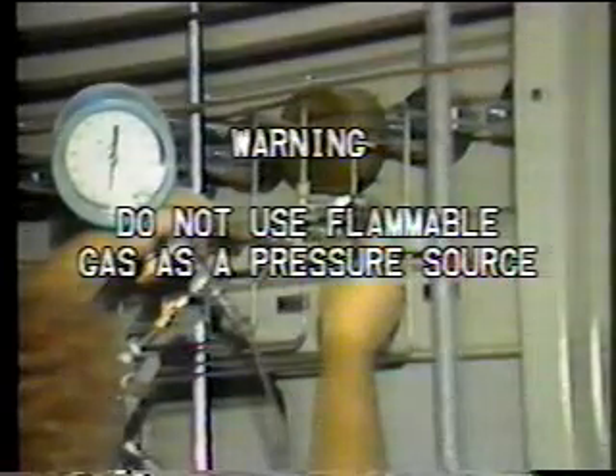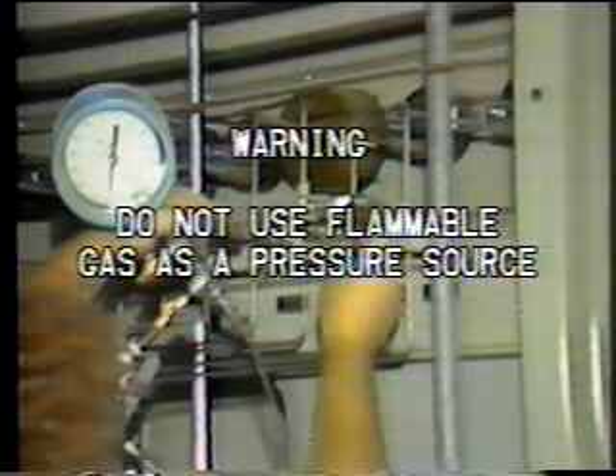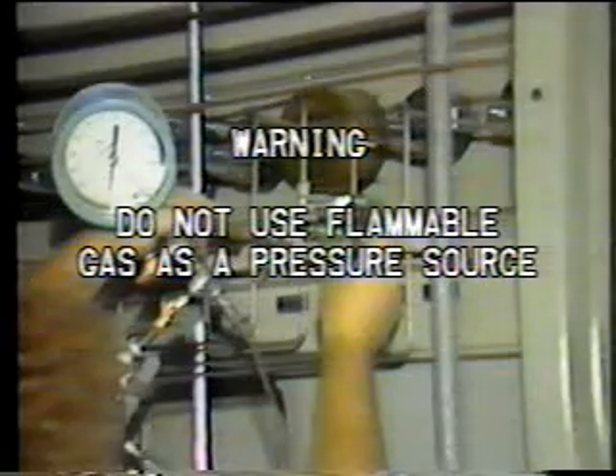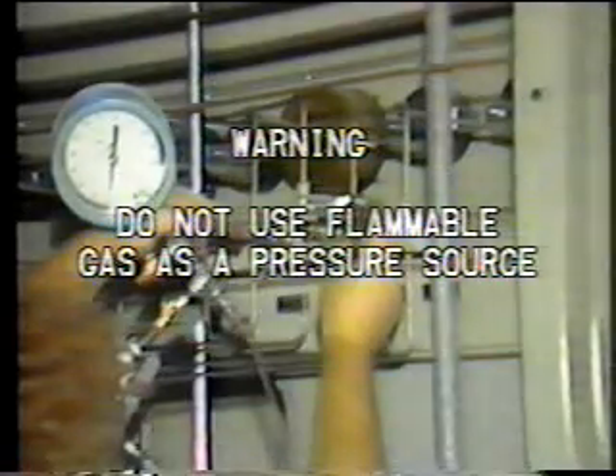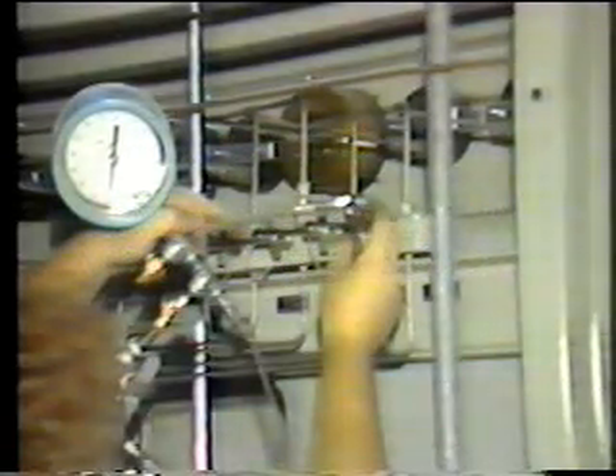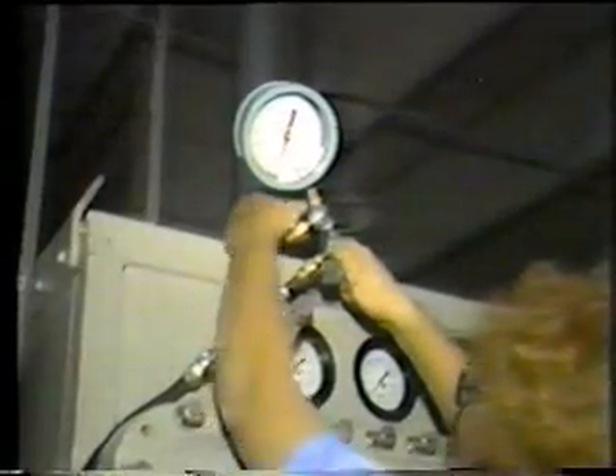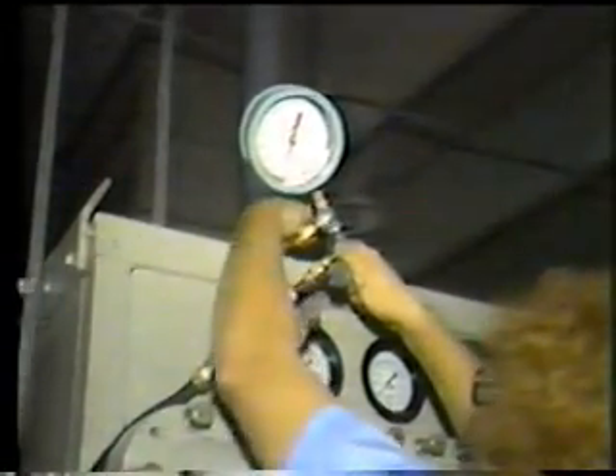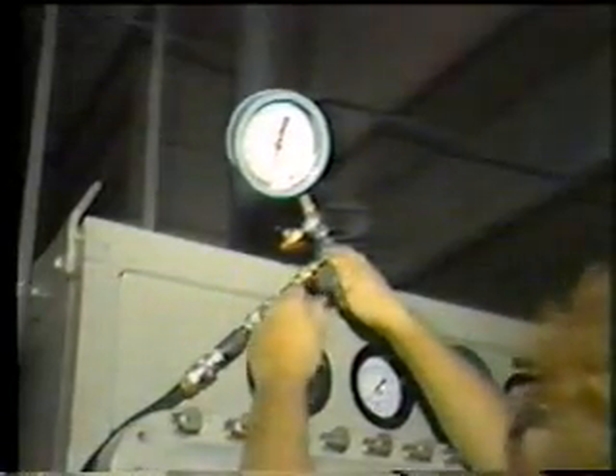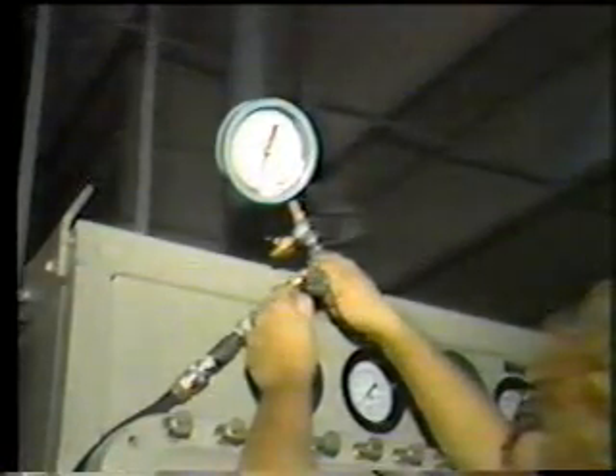Warning: do not use flammable gases as a pressure source. Their unstable characteristics create a safety hazard which could result in damage to the equipment and cause personal injury. In some cases, system pressure can be used as the pressure source. If system pressure cannot be used, an external pressure source must be supplied in order to perform gauge calibration. In this procedure, we will use an external pressure source.